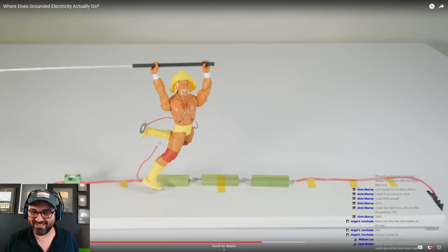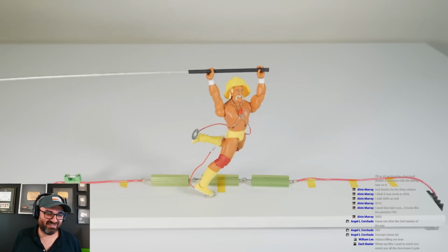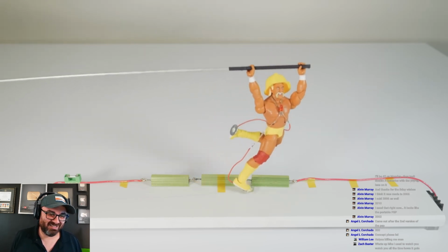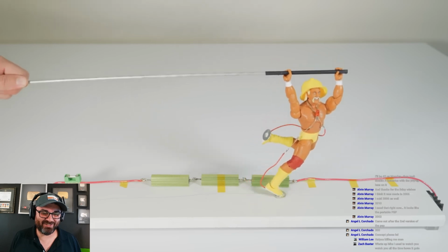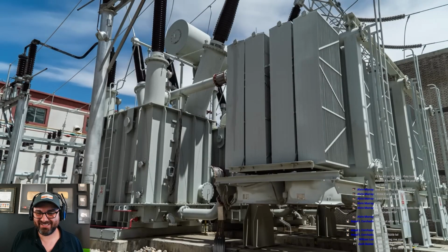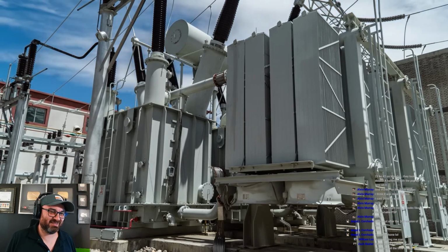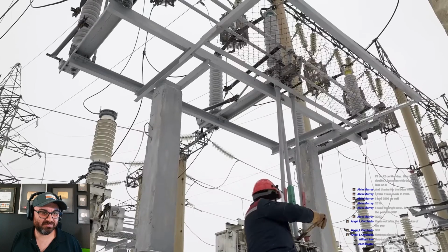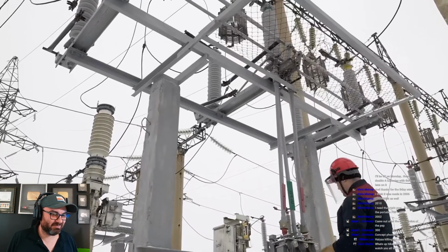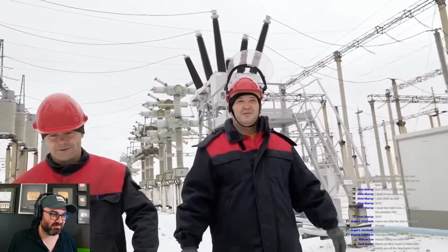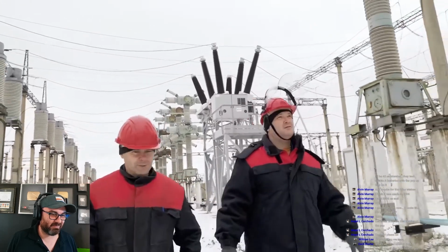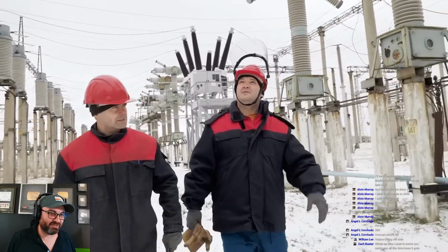Power line technicians are often encouraged to hop on 1 foot away from a ground fault to reduce the chance of a step potential. It sounds silly, but it might save their life. Similarly, power technicians often come into contact with the metal cases around equipment regularly. So, if a ground fault happens on a piece of equipment and the resistance of the grounding system is too high, there can be a voltage between the ground and the metal case, again creating the possibility of a voltage across a person's body, called touch potential. The engineers who design power plants, substations, and transmission lines have to consider what touch potentials and step potentials can be safely withstood by a person and design grounding systems that make sure they never exceed that level.